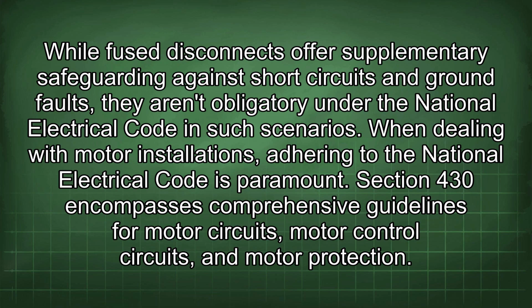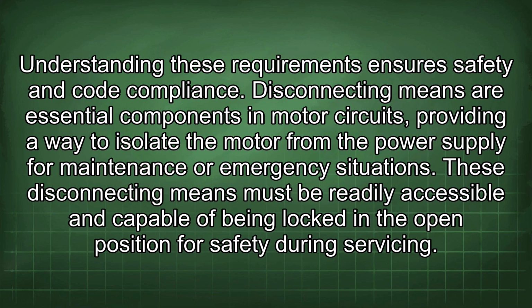Section 430 encompasses comprehensive guidelines for motor circuits, motor control circuits, and motor protection. Understanding these requirements ensures safety and code compliance. Disconnecting means are essential components in motor circuits, providing a way to isolate the motor from the power supply for maintenance or emergency situations.